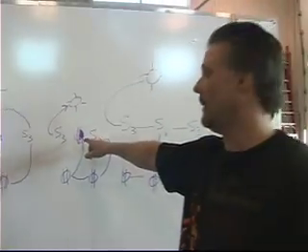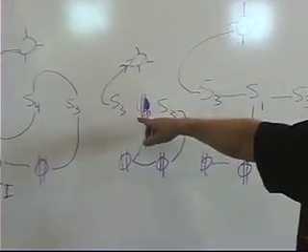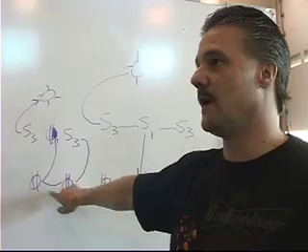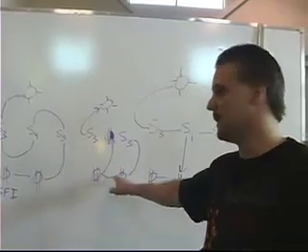Half the split outlet and the light — this side of the outlet is hot all the time. So you've got the three-ways turning the light on and off and controlling half the outlet, but these are hot all the time — they're not on the switch legs. So you've got to get the switch leg from here down to these two to control them.